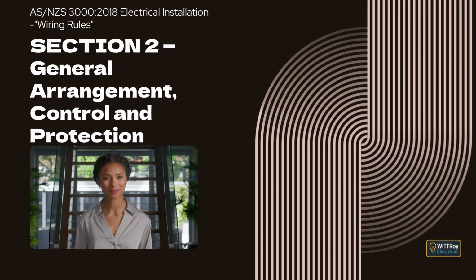These include enclosed fuse links that meet the correct standard, miniature circuit breakers, molded case circuit breakers, and fixed setting RCDs that meet their relevant standards. Other devices without auto-reclose may also be used if they have similar protection characteristics. Semi-enclosed rewirable fuses must not be used for automatic disconnection because they do not reliably clear faults in the required time. There is one exception. Some devices with auto-reclose may be used if they automatically test the insulation before reclosing, and only reclose when the insulation is safe.